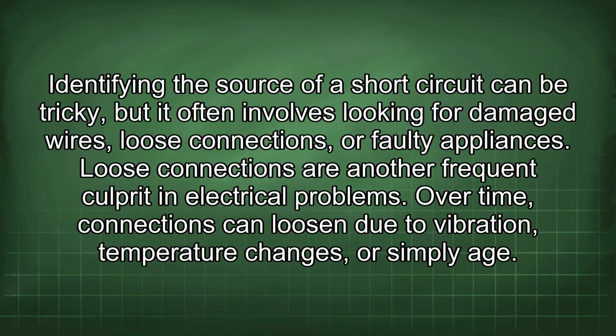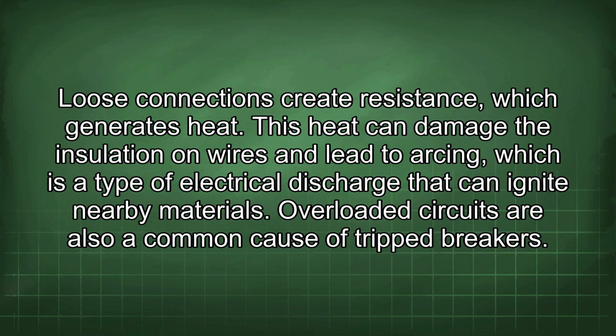Identifying the source of a short circuit can be tricky, but it often involves looking for damaged wires, loose connections, or faulty appliances. Loose connections are another frequent culprit in electrical problems. Over time, connections can loosen due to vibration, temperature changes, or simply age. Loose connections create resistance, which generates heat. This heat can damage the insulation on wires and lead to arcing, which is a type of electrical discharge that can ignite nearby materials. Overloaded circuits are also a common cause of tripped breakers.